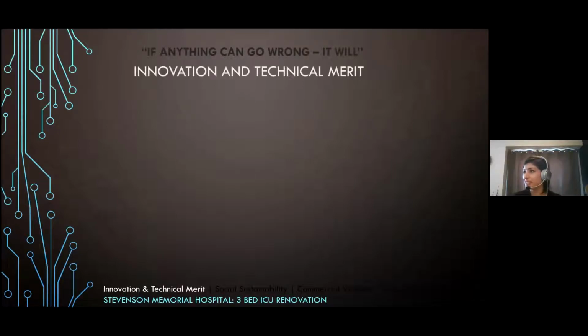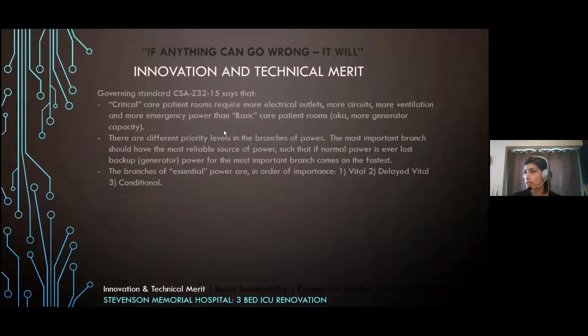Keeping Murphy's Law top of mind, technically speaking, what we had to accomplish was to meet CSA Z32, which outlines that critical care rooms differ quite a bit from basic care patient rooms in hospitals. Among other things, they require more electrical outlets, more circuits, more mechanical ventilation, and more emergency power than basic care rooms. But there are different levels of priority in the essential electrical system. CSA Z32 describes that the most important loads, if there's ever a power failure, should come back online via the generator the quickest. The order of importance is: vital loads are most important, followed by delayed vital, followed by conditional loads, which are a bit more discretionary.